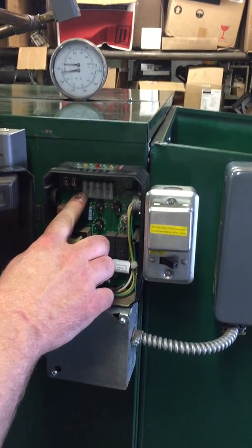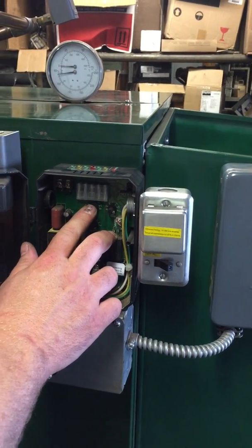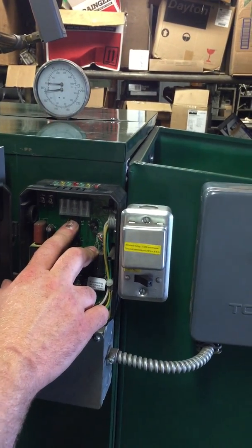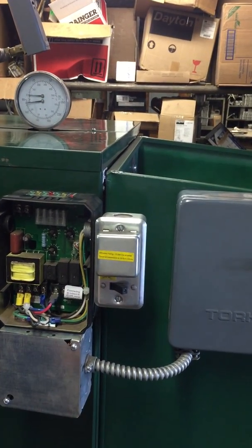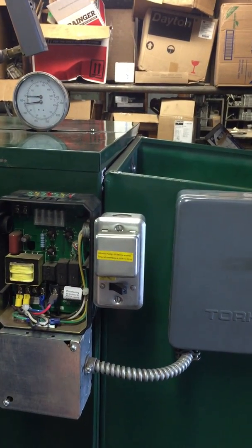As shown earlier in the video, we also covered setting the high and low temps. Once you light this and there is no thermostat call, it will run until it hits 140 degrees and then shut down the primary stoker unit. The secondary will stay running, and when you achieve 140 degrees is when all of that happens.